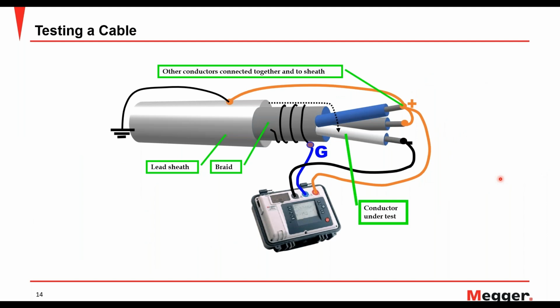Similarly, testing a cable. So you are hooking up your center conductor. I want to test white phase in this case. I'm hooking up my center conductor to the negative, and everything else I'm just hooking up to the positive, and I don't care about the surface discharge from here. So I'm just braiding a copper wire or any metallic conductor to the surface, and then I'm guarding it out so that any surface discharge I'm negating from the actual measurement. So that's how you test using a guard terminal. That's the actual use of guard terminal.